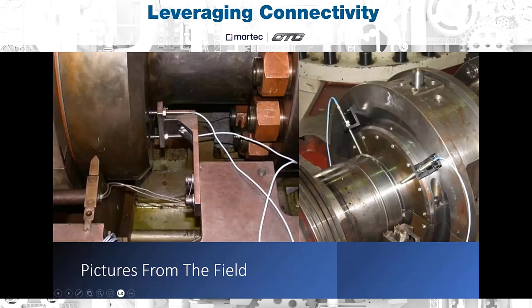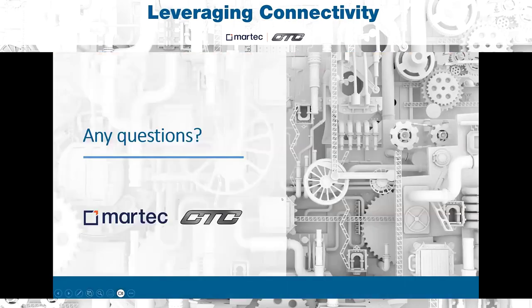On the right-hand side, we see 2 probes mounted 90 degrees apart from one another. This is what's called a radial mounting application. With this application, you can get the overall peak-to-peak vibration of the shaft being monitored here for condition monitoring purposes.